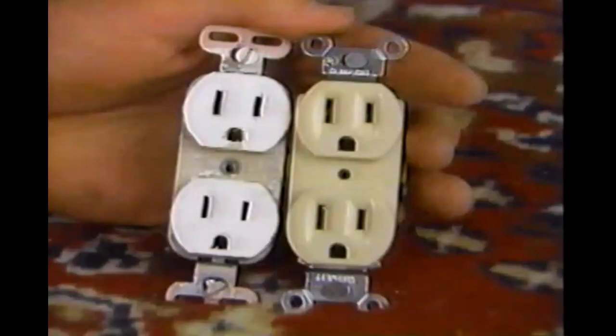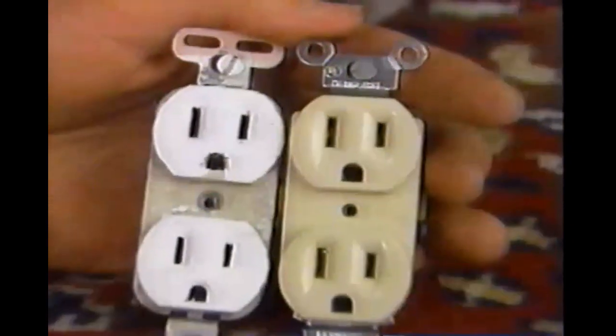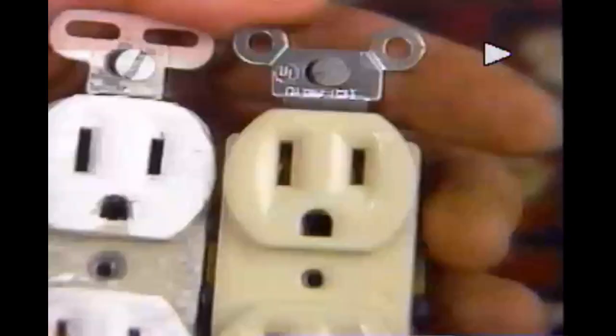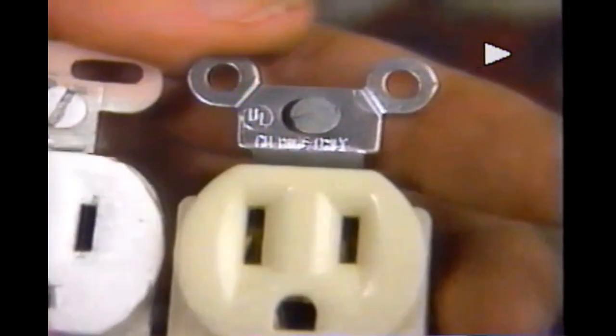It might help you to leave some wire attached when cutting the house wires. You can use that as a model by matching the colors. Brass screws are hot, white or silver are neutral, and green are ground. Because receptacles are rated for specific amperage, replace with an exact duplicate.